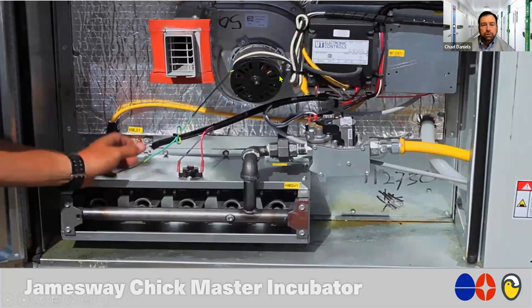You'll note that I mentioned earlier, you have to remove this because you visually can't see it without undoing a couple of bolts and pulling this out of the unit. But essentially the combustion blower doesn't do anything but draw fresh atmosphere air through this as ignition occurs and allows complete combustion of the flow of gas into the unit. So this gives you a really good view of a specific unit, but pretty much all gas-fired rooftop heating units have the same basic principle. Gas line, gas valve, combustion blowers, and then your main heat exchanger that is inside of the unit.